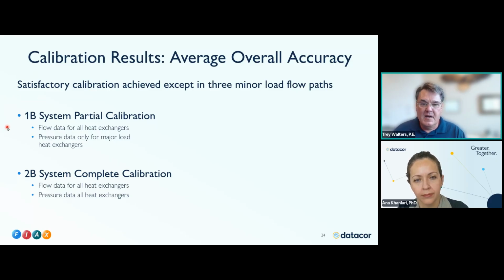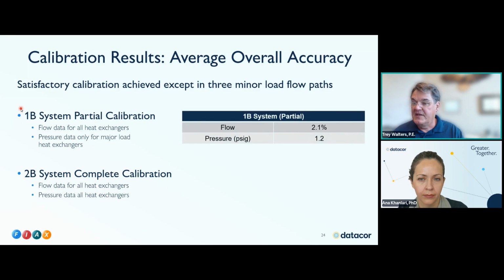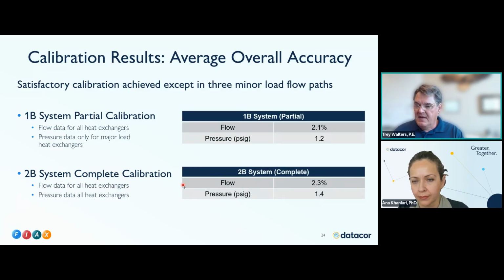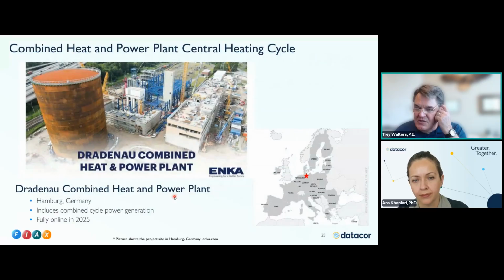So they had a 1B system partial calibration and a 2B system complete calibration is what we worked on. Satisfactory results. They really wanted to make sure their major heat exchangers were satisfactory, and the minor load flow paths were pretty good, but not 100%. It was a complex thing. But here's some of the results they got on the Unit 1B train. So we got flow balanced in the model by changing roughnesses and scaling and the ID on the pipe. Got it balanced within 2.1% in the model, and pressure within 1.2 psi. And then in the Unit 2B train, flow within 2.3%, pressure within 1.4 psi. Okay, let's move on to another case study.